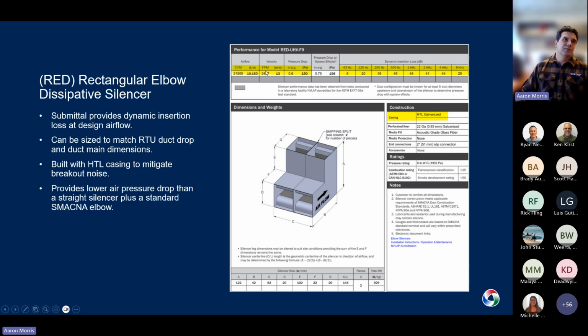In the submittal here, you can see we'll provide the air pressure drop at the design CFM, and then the insertion loss for each octave band will show the number of dBs that'll be reduced by using the silencer. The other thing to note here is in the construction of this silencer, we're using HTL casing, which is a high transmission loss casing, so the sound won't travel through that sheet metal. So it addresses that breakout noise path as well. With this silencer, we can cover both the ductborne noise and the breakout noise.